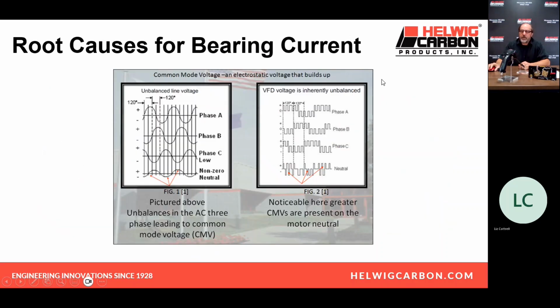What are the root causes of the bearing current that we see? Remember, we see a shaft voltage build and build and build until there's so much push behind the voltage that it'll arc through the bearing to ground. What's happening is there's an imbalance between the three phases of power going from the motor drive to the motor. This imbalance comes from a digital version of the three phases. The digital version is each phase is out of phase with each other, but also out of balance with each other. This imbalance between the phases causes a cumulative effect called common mode. The common mode builds on the shaft, builds, discharges through the bearing. It causes premature bearing failure.